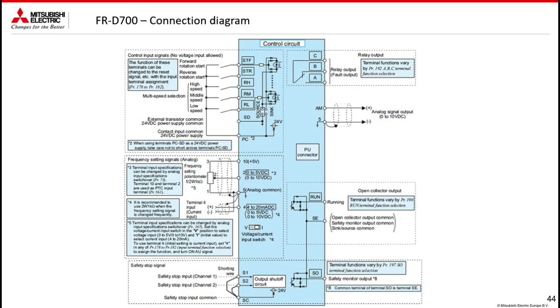Now moving on to the outputs, there is A, B, C available, which is a relay. C is the reference common to which I will bring the power supply. A normally open and B normally closed. By default, it works on the error, so when an error occurs, A closes and B opens. This can also be parameterized. AM analog output from 0 to 10 volt reference based by default on the output frequency 0 to 50 Hz.